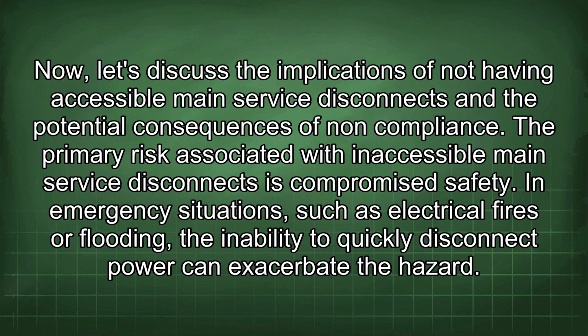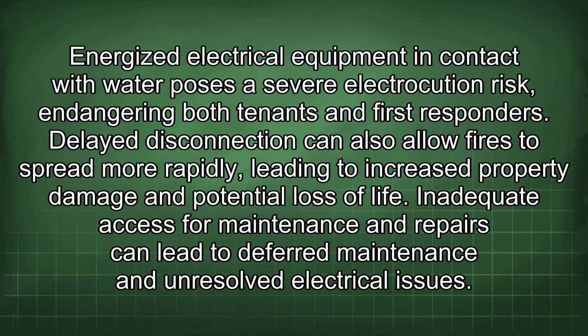Now let's discuss the implications of not having accessible main service disconnects and the potential consequences of non-compliance. The primary risk associated with inaccessible main service disconnects is compromised safety. In emergency situations such as electrical fires or flooding, the inability to quickly disconnect power can exacerbate the hazard. Energized electrical equipment in contact with water poses a severe electrocution risk, endangering both tenants and first responders. Delayed disconnection can also allow fires to spread more rapidly, leading to increased property damage and potential loss of life.